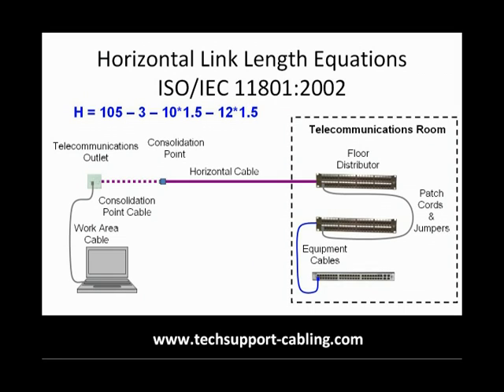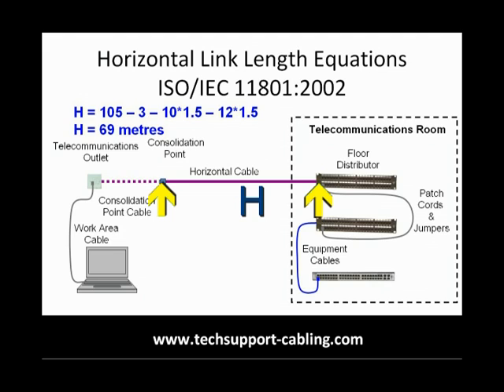H, which remember is the maximum permissible horizontal cable length, equals 105 minus 3, which is 102, minus 15, which is 87, minus 18 — giving us a length for H of 69 metres.